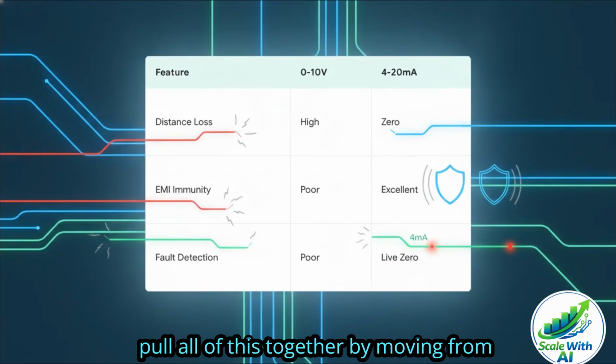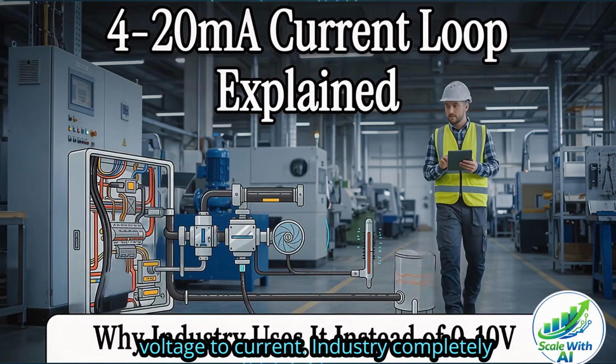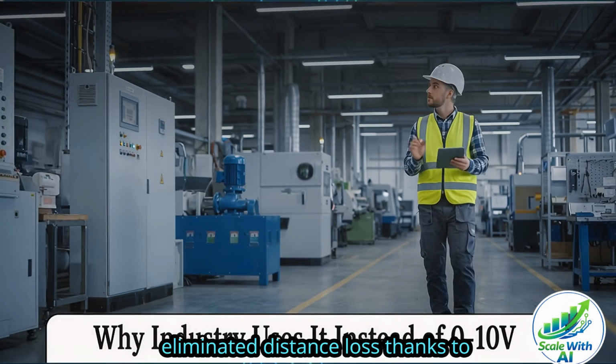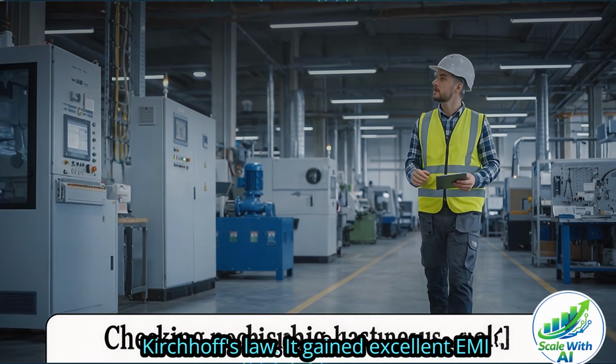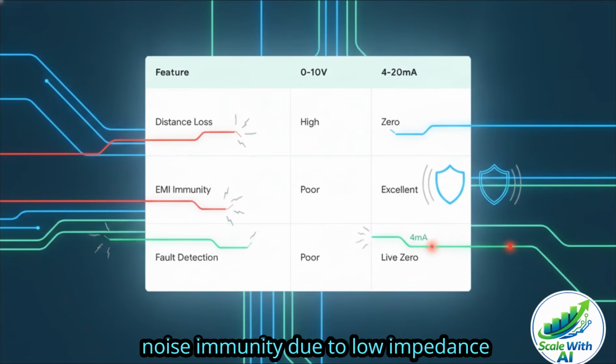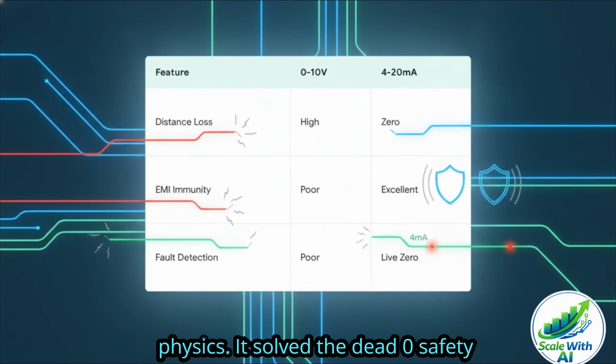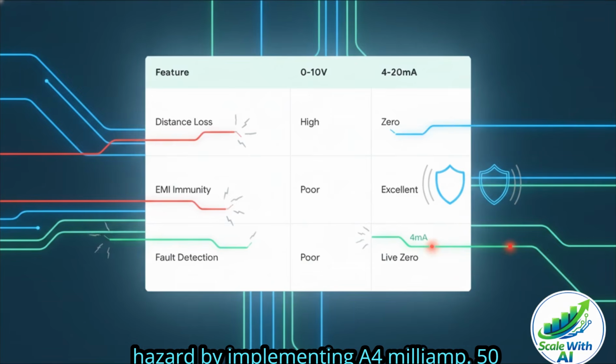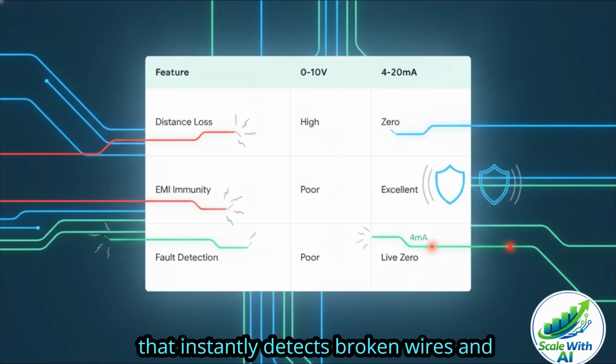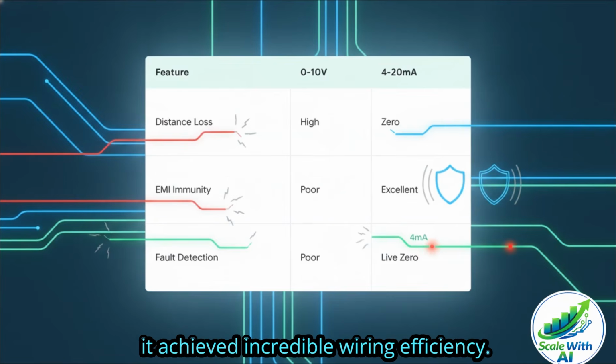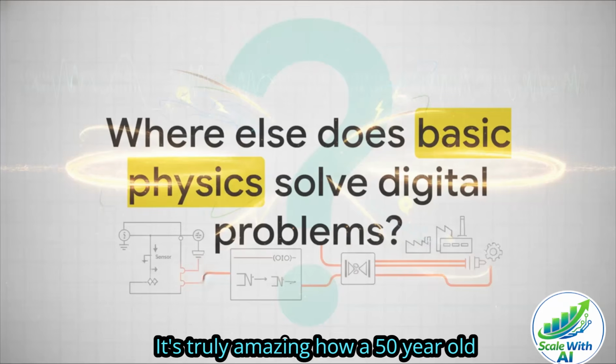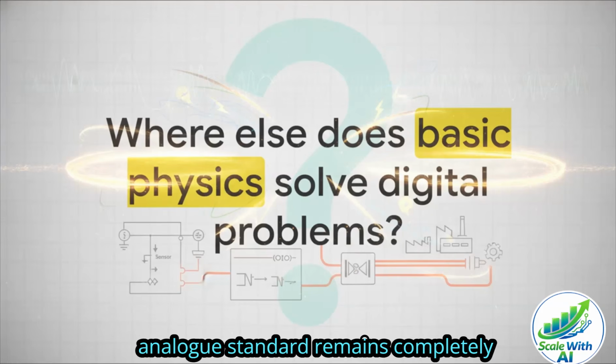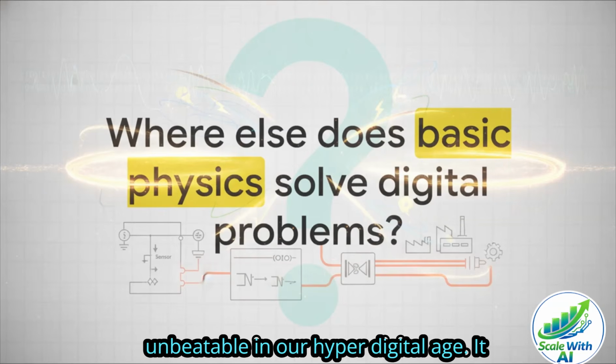Okay, let's pull all of this together. By moving from voltage to current, industry completely eliminated distance loss thanks to Kirchhoff's law. It gained excellent EMI noise immunity due to low impedance physics. It solved the dead zero safety hazard by implementing a 4 milliamp live zero that instantly detects broken wires. And it achieved incredible wiring efficiency. It's truly amazing how a 50-year-old analog standard remains completely unbeatable in our hyper-digital age.